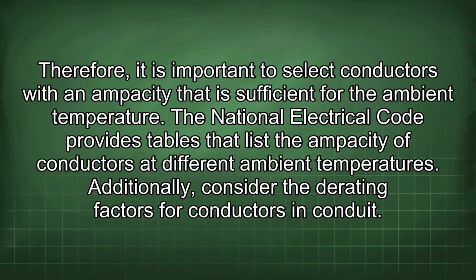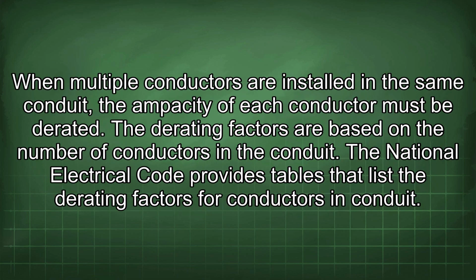Additionally, consider the derating factors for conductors in conduit. When multiple conductors are installed in the same conduit, the ampacity of each conductor must be derated. The derating factors are based on the number of conductors in the conduit. The National Electrical Code provides tables that list the derating factors for conductors in conduit.